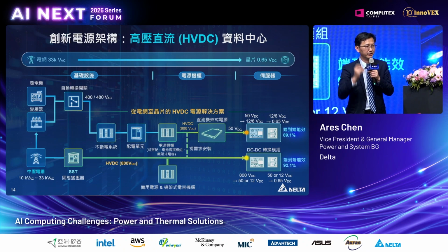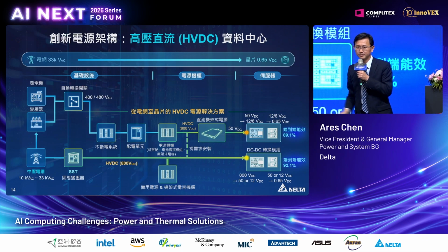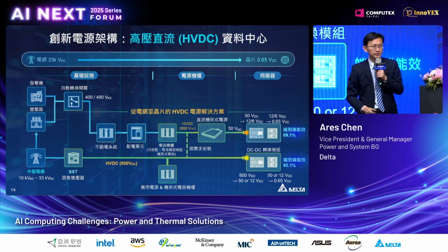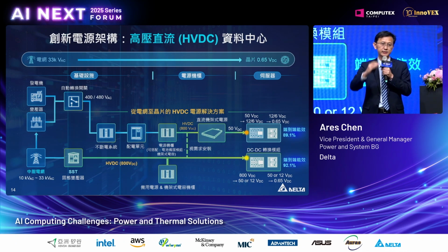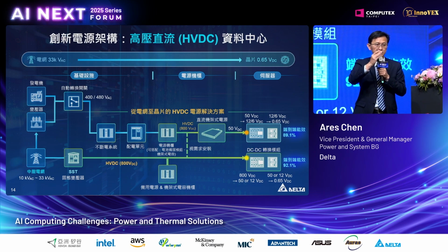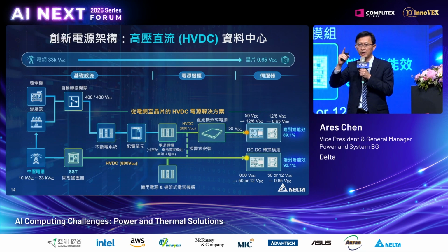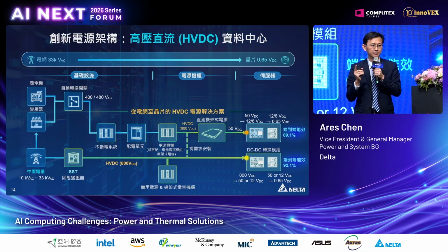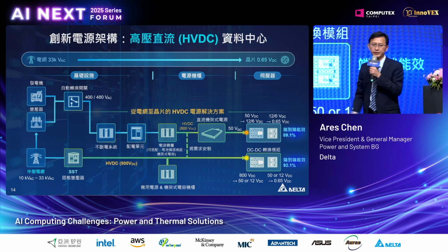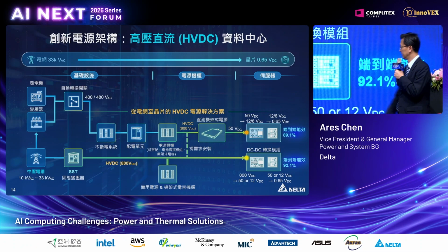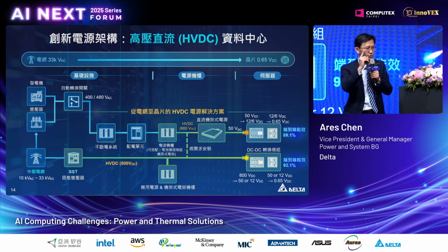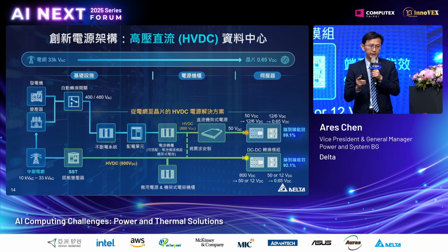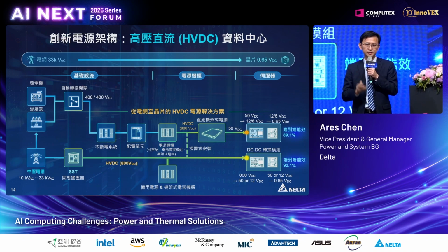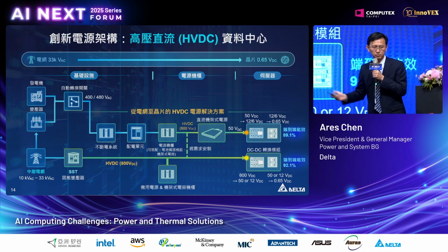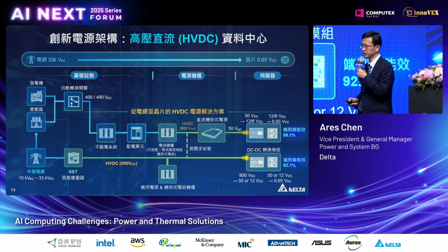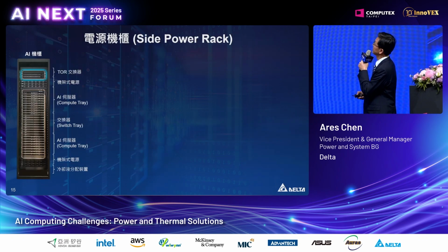So all of these blocks have been skipped. We concentrated them into this solid-state transformer. It's like using the 33 kV to power electronics to reduce it to 800 volt DC. So that's one goal: 800 VDC, and then it will be distributed with PDU and PSU. We estimate that this will be 92% power efficiency, around a 4.5% increase. We think this will be a huge help for future power consumption.